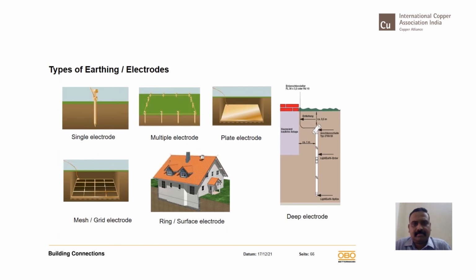Right. So there are questions which arise with people, like, can we take an option between the earthing, sir? There are several types of earthing system. If the resistance value is not achieved, why can't I try a plate earthing? No. Different types of earthing are practiced, yes, for different applications. Now, if your intention is to have the least resistance, remember, going deeper and deeper can only achieve the least soil resistivity, out of which your least resistance can be obtained. So if your intention is to achieve the least resistance, a single driven rod with a deeper length can help you in bringing down the resistance to a great extent.